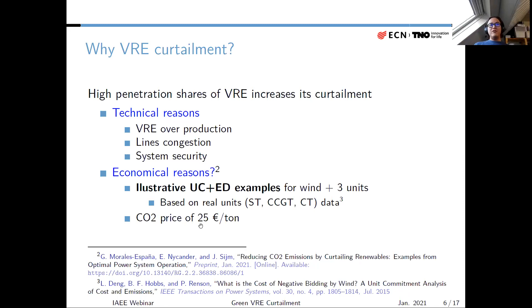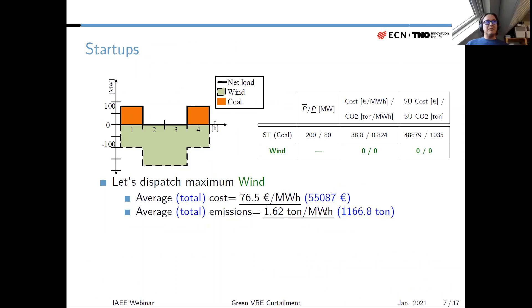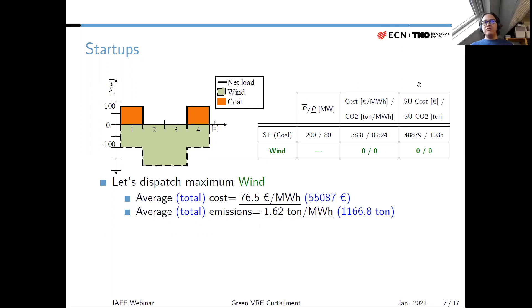For these examples, there is a CO2 price of 25 euros per ton already internalized in the bids. The cases are based on realistic data taken from the referenced paper. Let's start with the first example — it's about startup of units. Here we have a residual or net load shown as the solid black line, which is what remains after wind is producing at maximum. The other unit is a coal unit with maximum output of 200 MW, minimum output of 80 MW, and variable cost of 38.8 euros per megawatt hour.